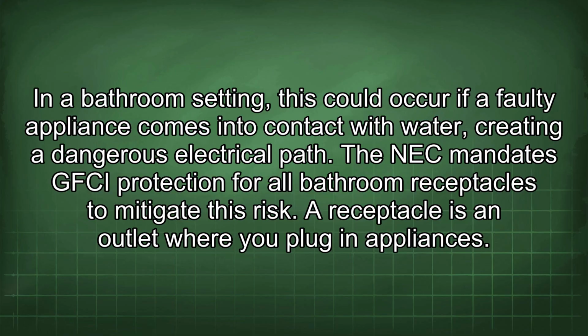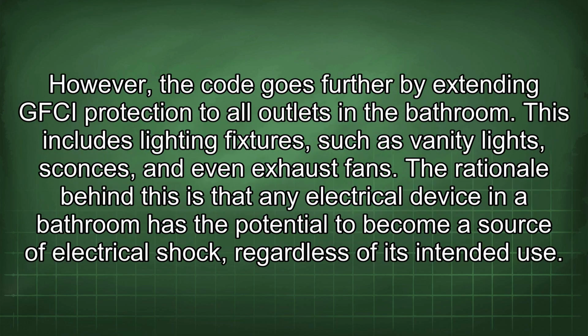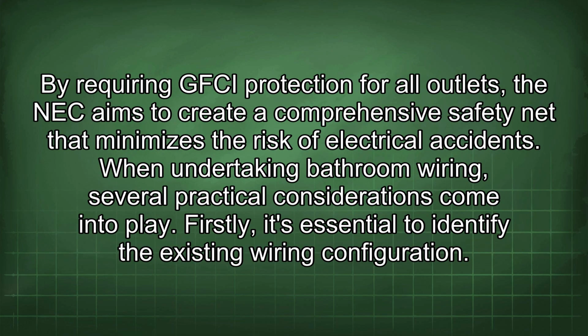A receptacle is an outlet where you plug in appliances. However, the code goes further by extending GFCI protection to all outlets in the bathroom. This includes lighting fixtures, such as vanity lights, sconces, and even exhaust fans. The rationale behind this is that any electrical device in a bathroom has the potential to become a source of electrical shock, regardless of its intended use. By requiring GFCI protection for all outlets, the NEC aims to create a comprehensive safety net that minimizes the risk of electrical accidents.